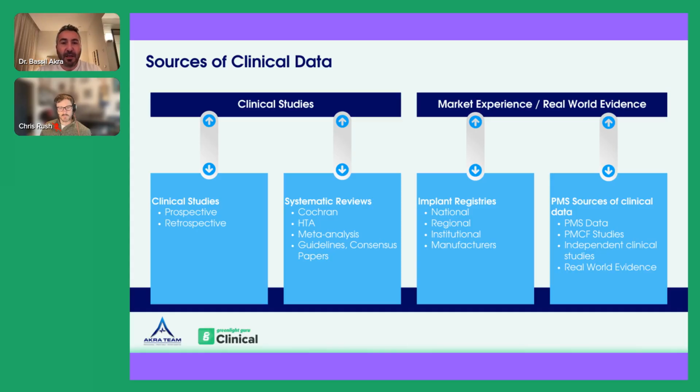And this is very key because not all data are important. So I saw a lot of manufacturers doing surveys just to satisfy the request of a notified body. And some of these surveys were actually good. Some others were very bad because they were just saying, do you like my packaging? Do you like the color of our labeling? This is not clinical data. This is not adding value. So if you do a survey, you need to do it in a way which is reasonable.